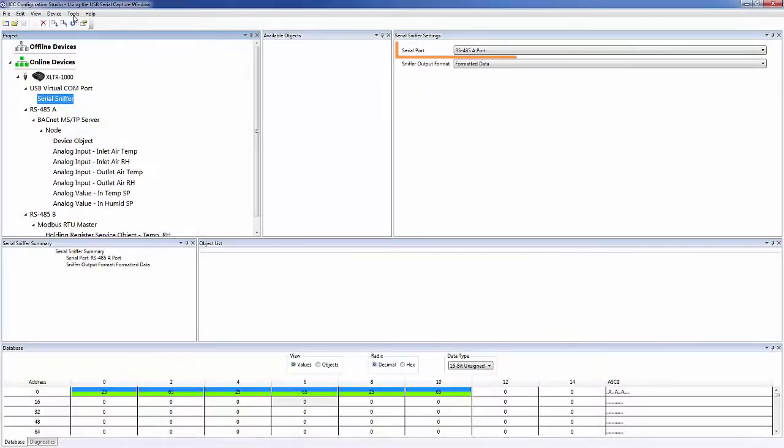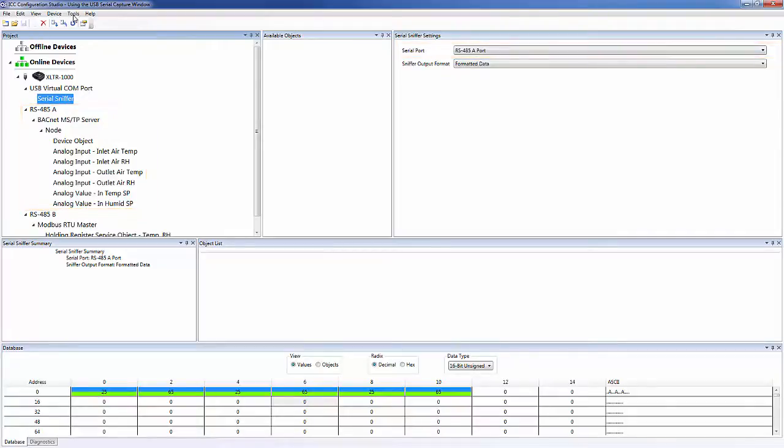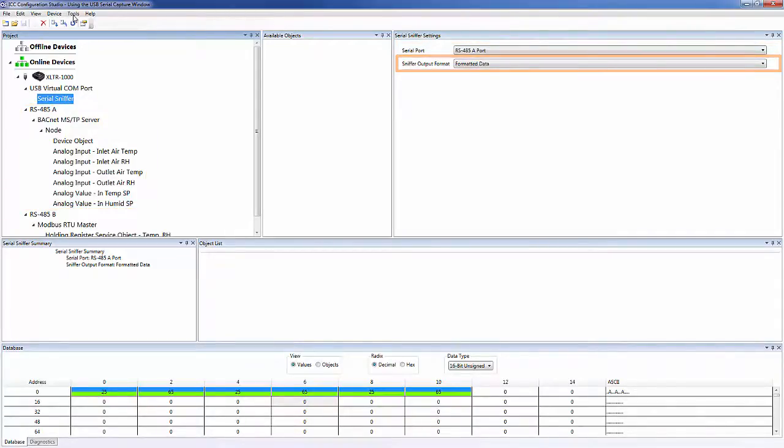We have selected the serial port which corresponds to the port that is configured for BACnet MSTP. We also have the sniffer output format set to Formatted Data. This option must be selected in order to use the USB Serial Capture Window.